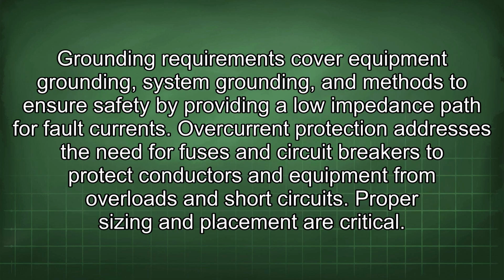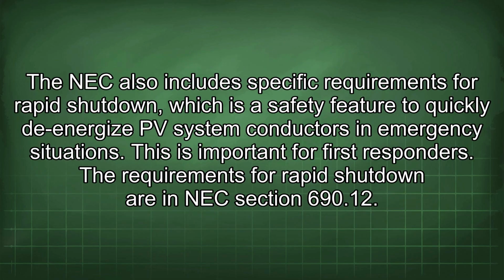Grounding requirements cover equipment grounding, system grounding, and methods to ensure safety by providing a low impedance path for fault currents. Overcurrent protection addresses the need for fuses and circuit breakers to protect conductors and equipment from overloads and short circuits. Proper sizing and placement are critical. The NEC also includes specific requirements for a rapid shutdown, which is a safety feature to quickly de-energize PV system conductors in emergency situations. This is important for first responders. The requirements for rapid shutdown are in NEC section 690.12.